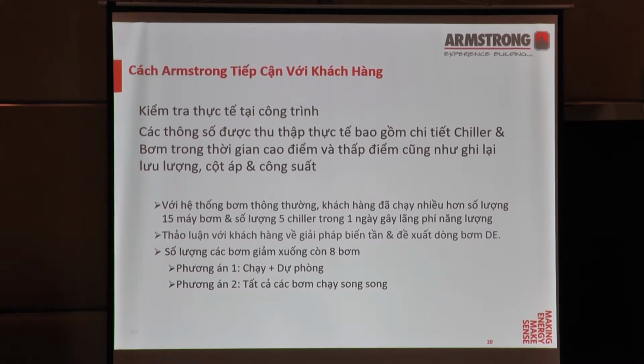So the discussion we have with the customer is, how do we resolve that? When you change to a variable primary flow and use an integrated control with our DE pumps, what we actually help you do is reduce the number of pumps, sizing it down to 8. Here you see there are 2 options we propose. The first one, of course, is that customers are very much aware of duty standby, so we propose using our DE pumps with a duty and standby solution. Or we propose all the pumps running in parallel, which you have just learned.